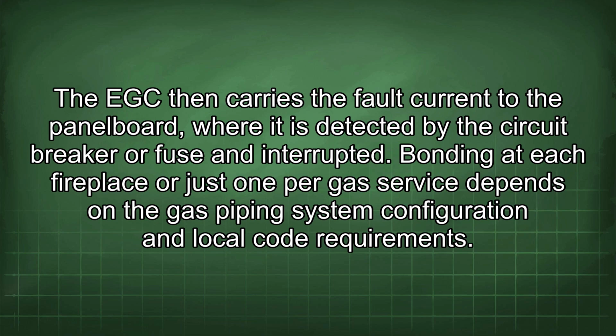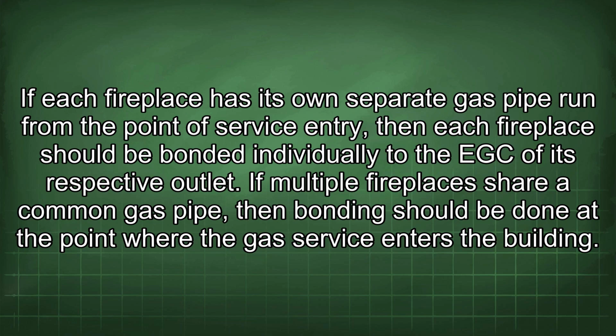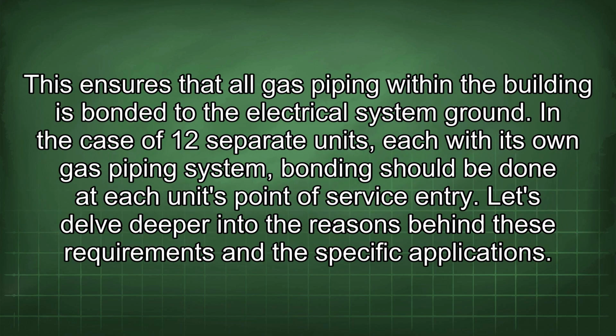Bonding at each fireplace or just one per gas service depends on the gas piping system configuration and local code requirements. If each fireplace has its own separate gas pipe run from the point of service entry, then each fireplace should be bonded individually to the EGC of its respective outlets. If multiple fireplaces share a common gas pipe, then bonding should be done at the point where the gas service enters the building. This ensures that all gas piping within the building is bonded to the electrical system ground. In the case of 12 separate units, each with its own gas piping system, bonding should be done at each unit's point of service entry.